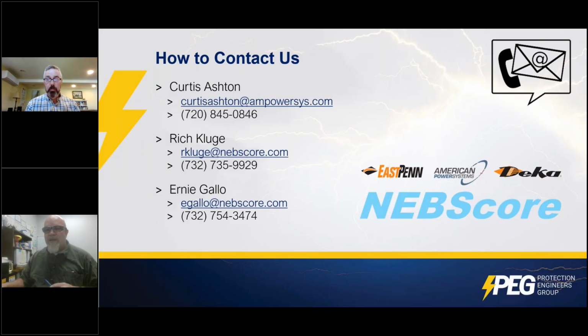Question number two is, do lead acid and NiCad that are bigger than 48 volts DC and greater than 70 kilowatt hours require the UL 9540 testing or the UL 1973 listing to exempt them from the 3-foot separation requirement? And in the latest editions of NFPA 855, no, but to Rich's point just a minute ago, it depends on what fire code is adopted. If it's not up to date, addressing the latest one, you may have an AHJ that may require you to do certain things. I've had success in showing AHJs, fire marshals, and architecture and engineering firms that, hey, here's where the code was, here's where it's going, and some of them will back off then and say, okay, we see where the code's going, and that's where we want to do it. So yes, they are exempt in the latest edition of the standard, but not necessarily in the code that's adopted in your jurisdiction.